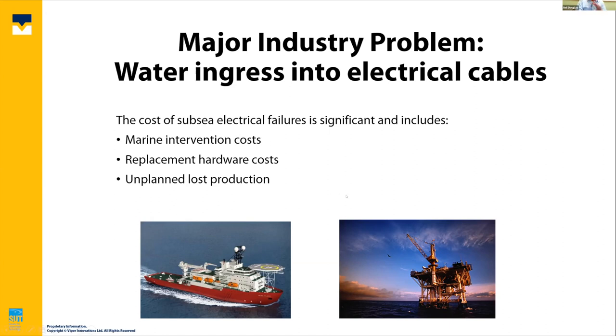Now, I've told you the mechanism where low insulation resistance may ultimately result in a complete failure. What I've shown is the worst case, where all the copper loss is at a single point. If you have general water ingress along the length of the cable, then the copper loss is going to be along the length of the cable, and so the rate of reduction of the cross-sectional area is going to be that much slower.